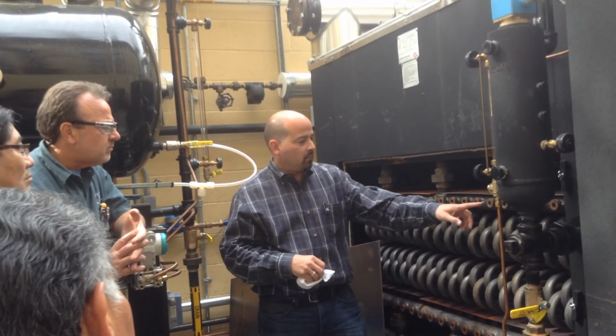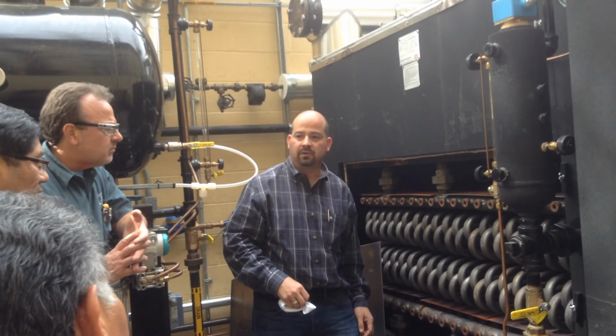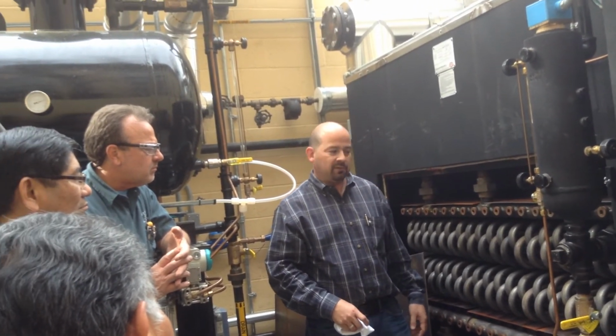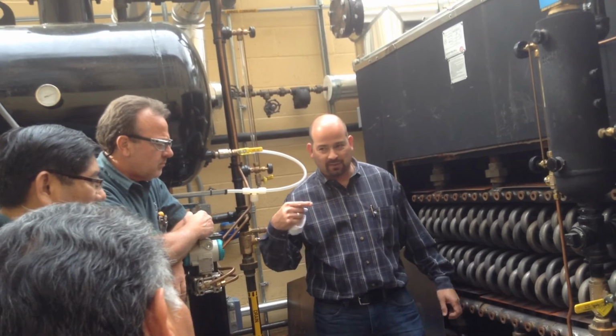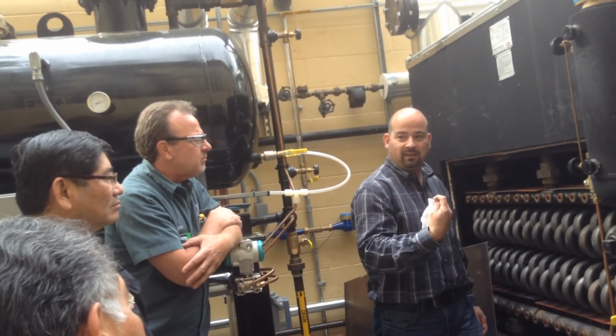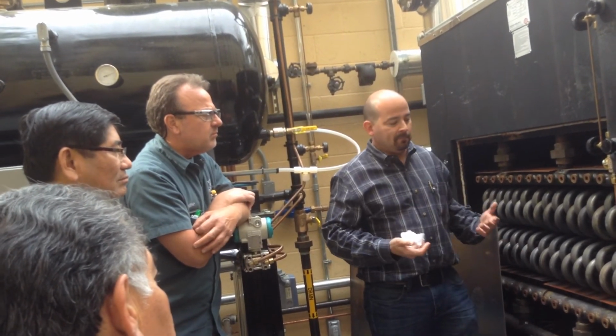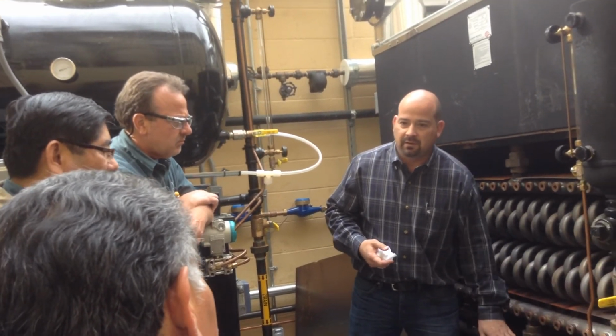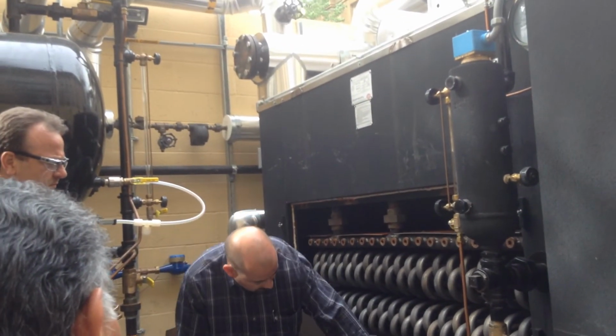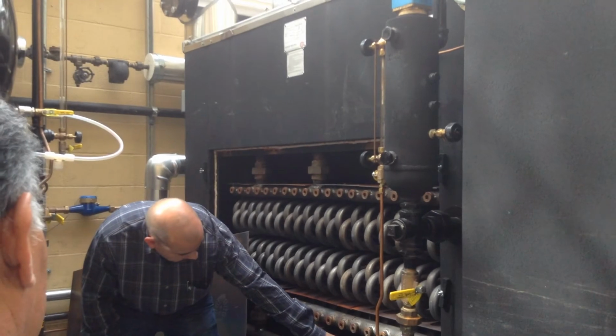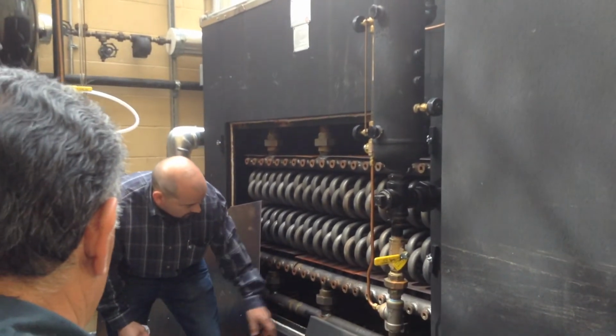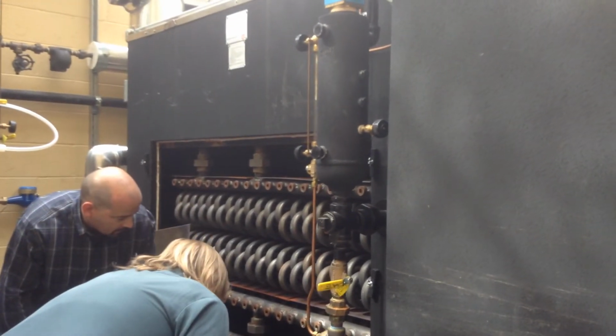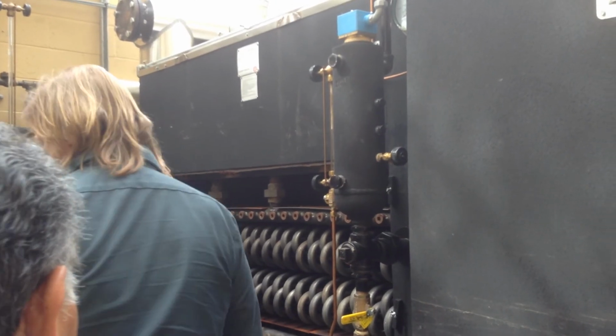I recommend maybe one up here, one down here when you do your preventative maintenance, just to see what's going on in the bundles. You can only see the straight run. After the first bend, you're not going to see anything anyway, but usually if you're going to get any buildup, it's down here. So these are your burners. The expensive ones I was telling you about. So those are metal fiber mesh burners. So I'm going to go ahead and cycle it so you can see it fire up.